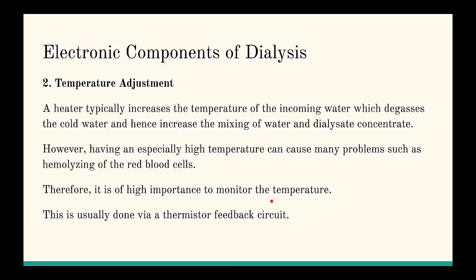Now, temperature adjustment. In the dialysis procedure, water is heated for several reasons. One reason is that cold water coming in is combined with dialysate, but we have to degas it to make sure it doesn't have too much air in it. We also want to increase mixing of the water and dialysate concentrate, which is another reason we heat it.